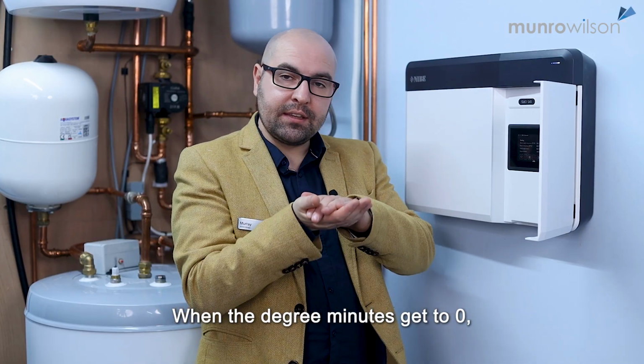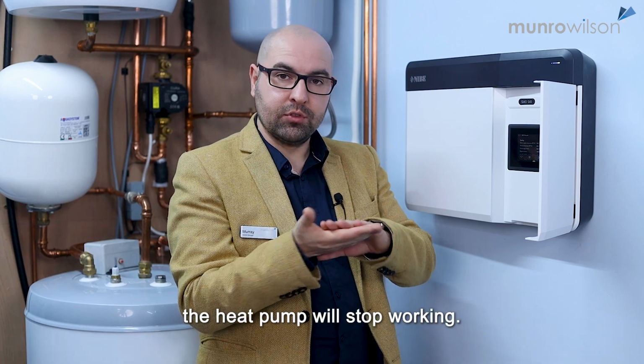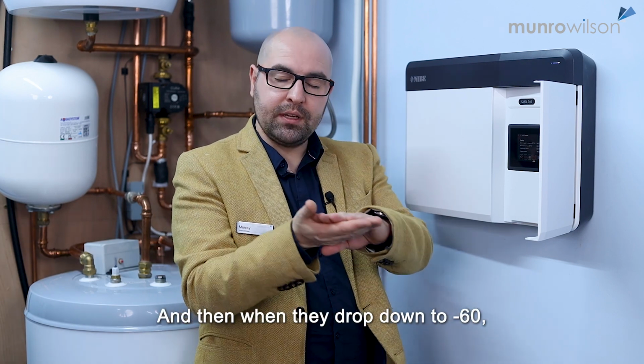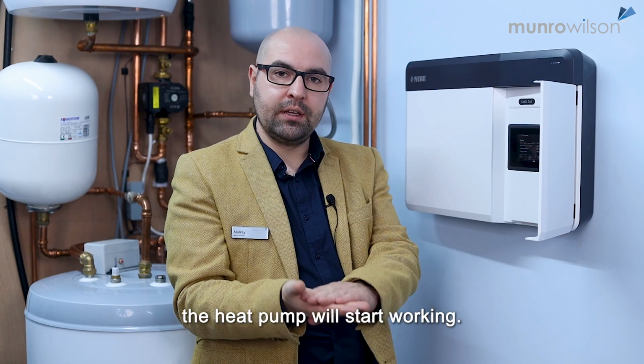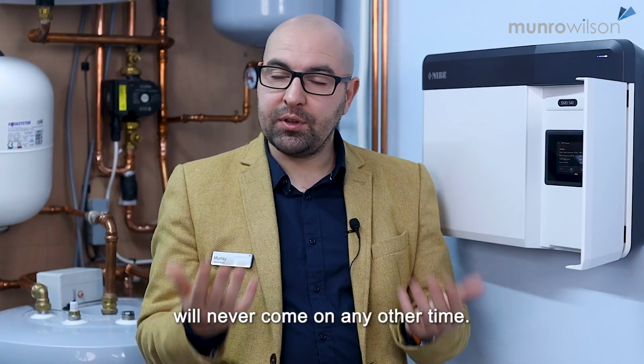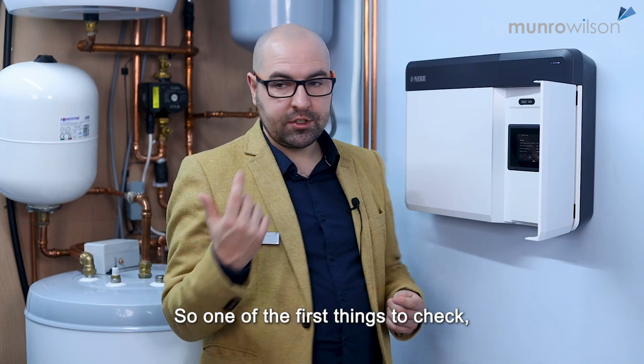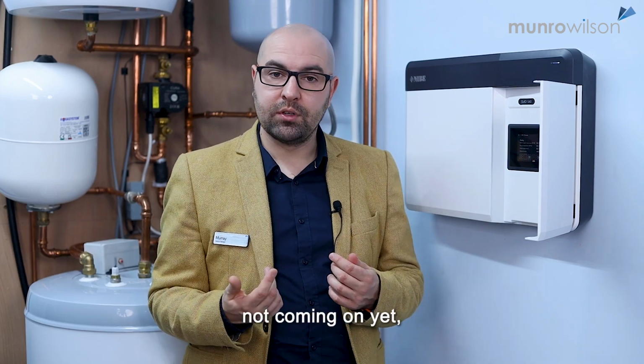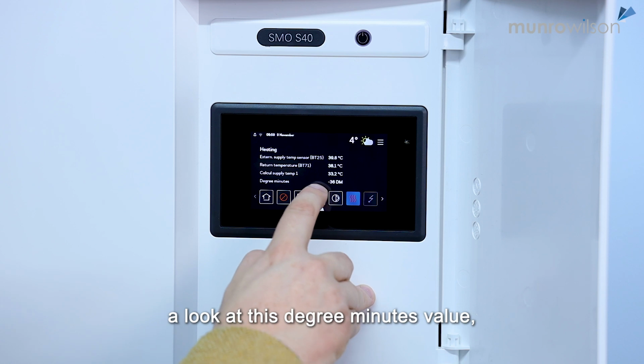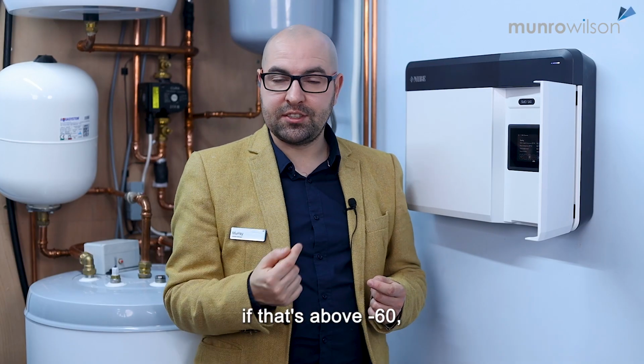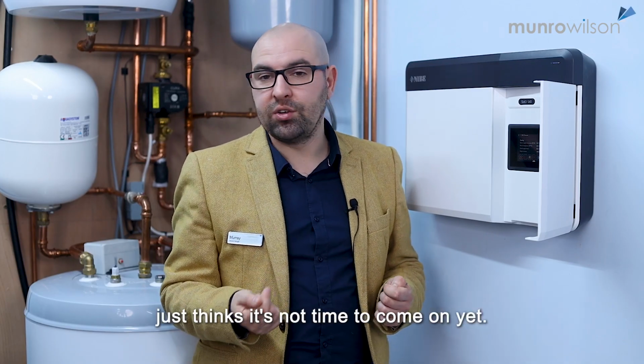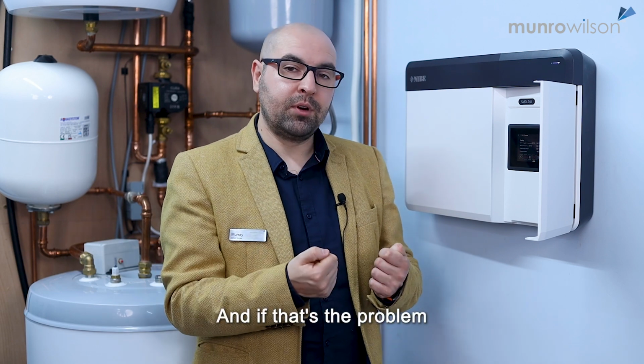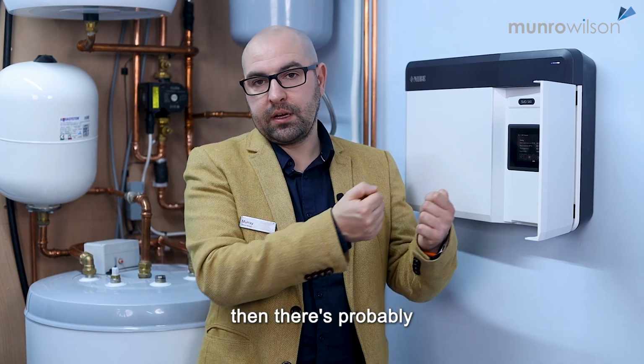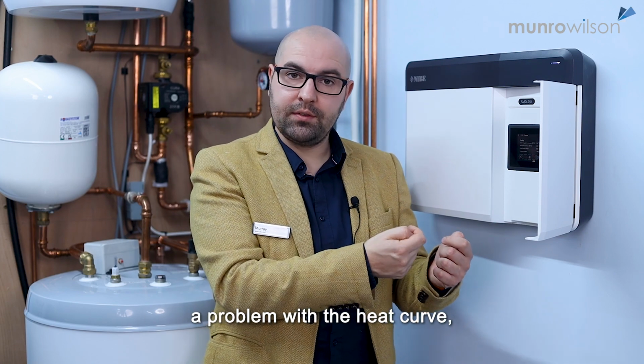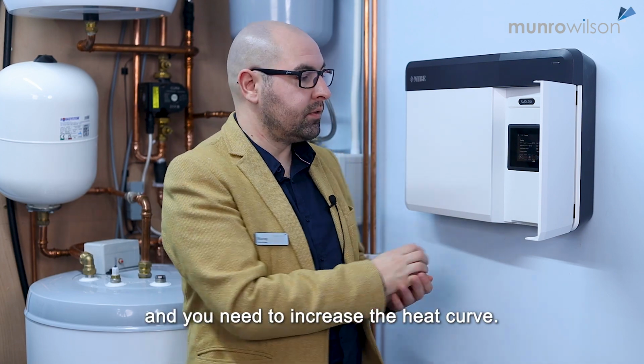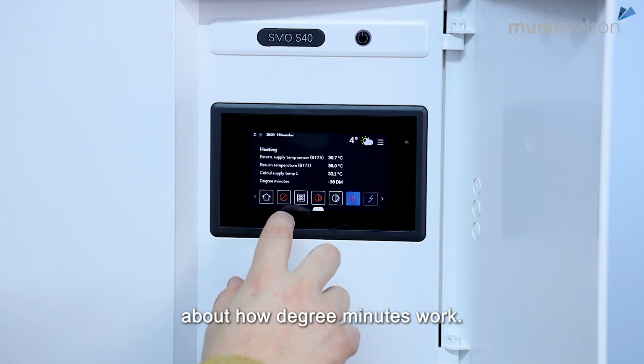When the degree minutes get to 0, the heat pump will stop working, and then when they drop down to -60, the heat pump will start working. And the heat pump will never come on any other time. So one of the first things to check if you're wondering why your heat pump's not coming on yet is to have a look at this degree minutes value. If that's above -60, the heat pump just thinks it's not time to come on yet. And if that's the problem that you're facing, then there's probably a problem with the heat curve, and you need to increase the heat curve.